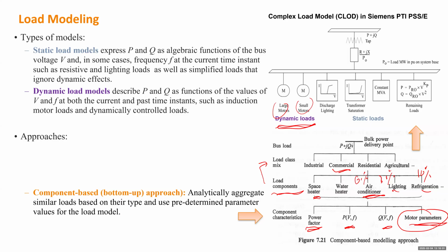So this is a bottom-up approach. This is a very classical approach adopted by the industry, the power system engineers. If you have a new region and you want to create a model, usually this is a necessary practice to understand the region better and build up the load model. Once they finish this at the site, they don't have to do it every year or often. You can just utilize the load model structure you created, and every year maybe you just need to do some update on the parameters.